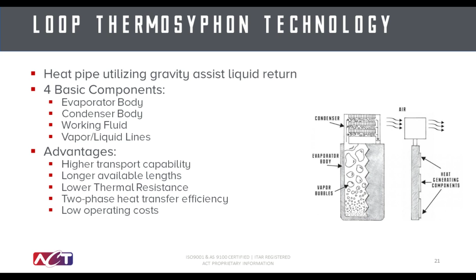The same expansion of vapor in the evaporator, combined with the condensation of liquid in the condenser, generates a gravitational pressure imbalance that naturally maintains fluid circulation between the condenser and evaporator. A substantial amount of waste heat is transferred using this natural circulation, since the latent heat of evaporation of the working fluid is large. The result is an extremely high-performance cold plate that requires no moving parts.